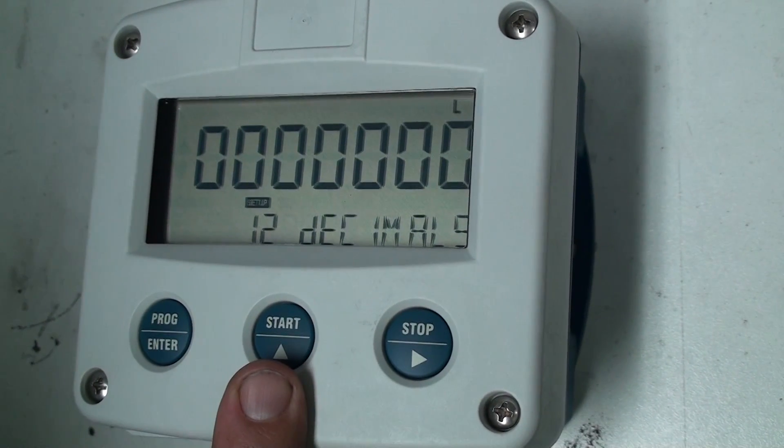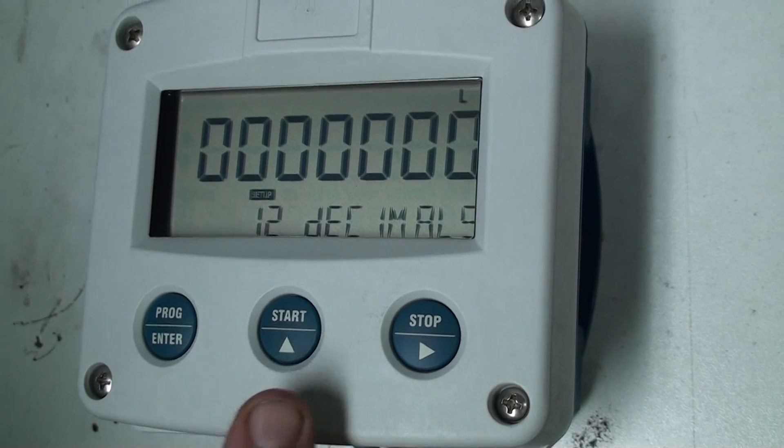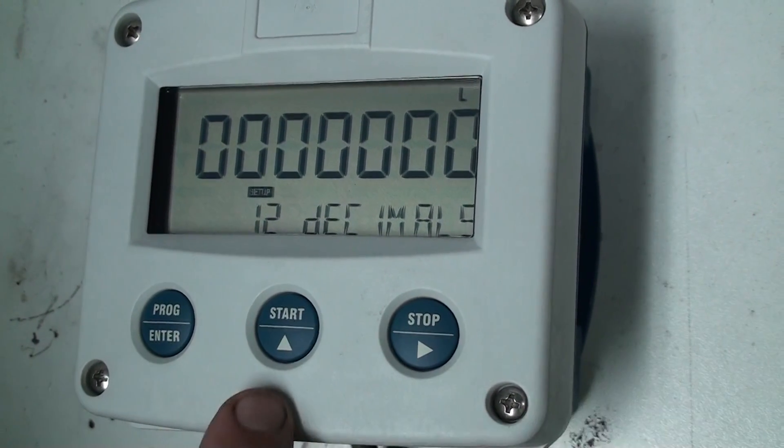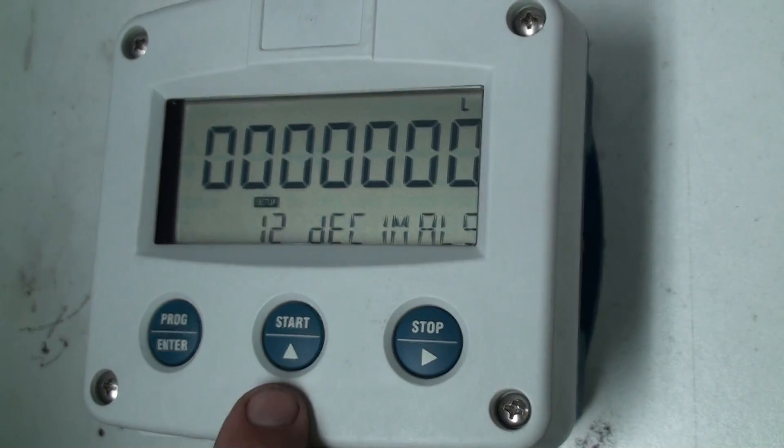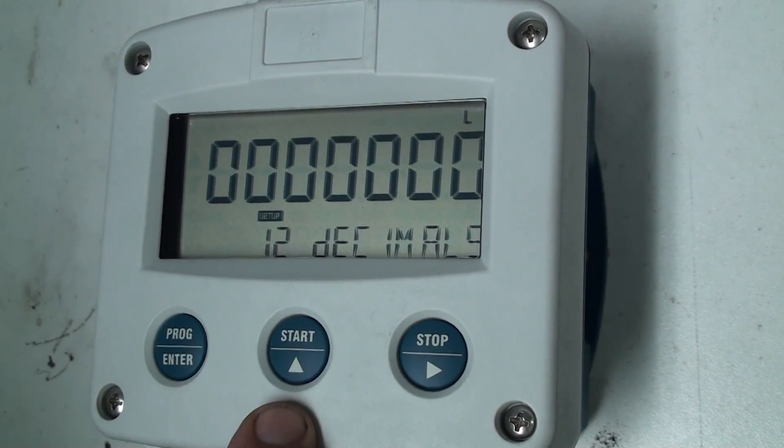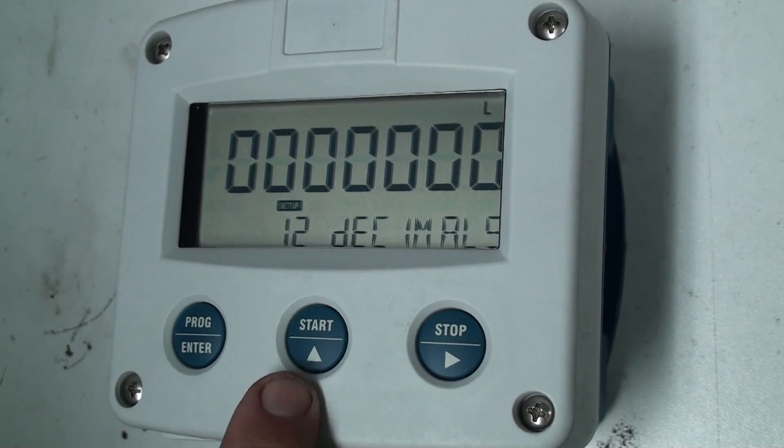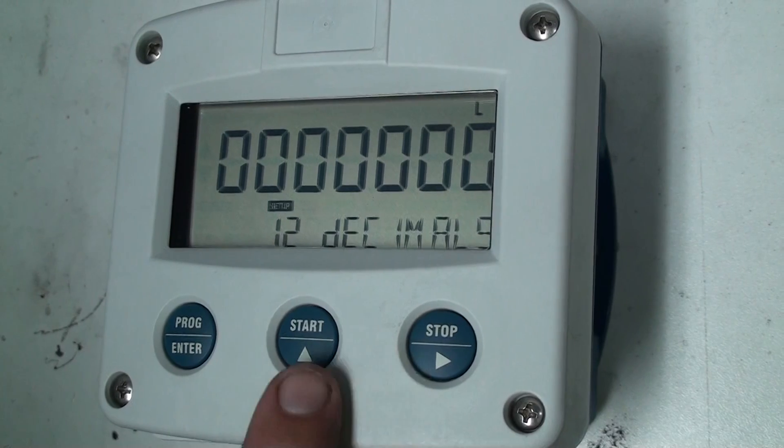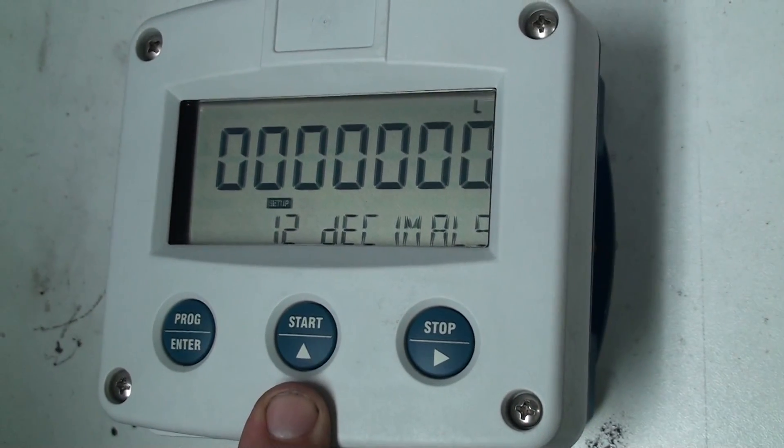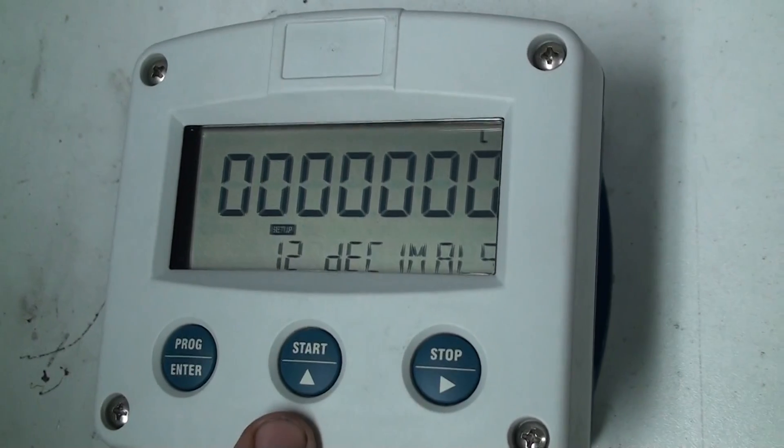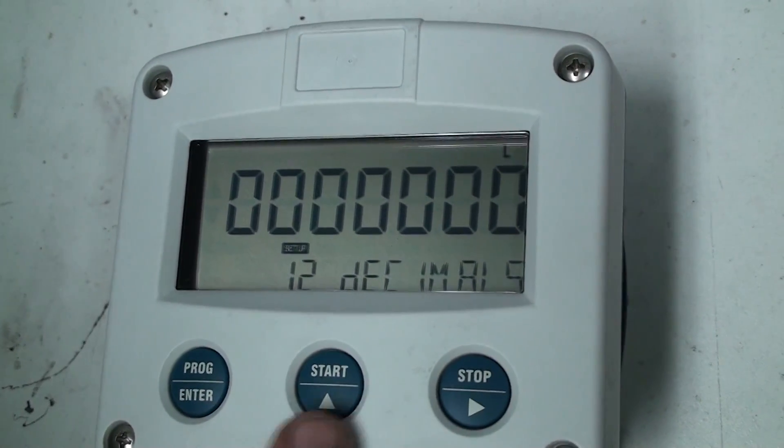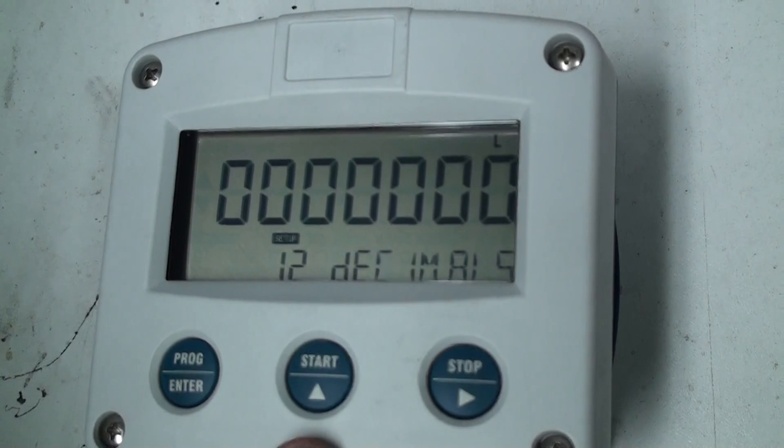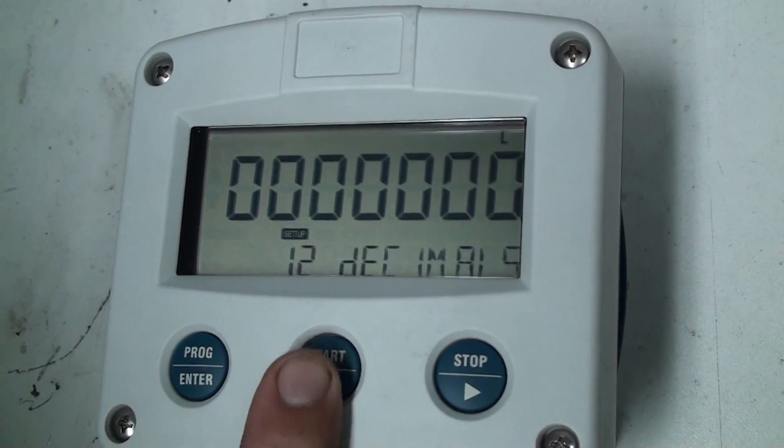12 is for decimal places. Now we will program this to be a 2 inch meter. Because we're going to be up to 300 liters per minute we don't want to have any decimal points. If we're using a small flow meter like a half inch you might want to put one decimal point but we'll leave it at no decimal points.